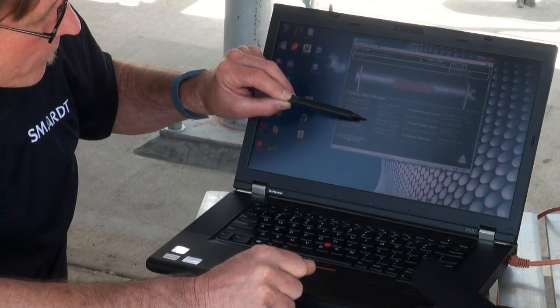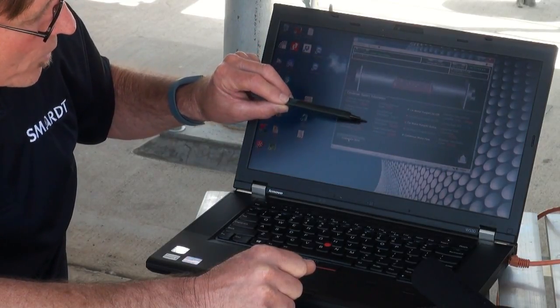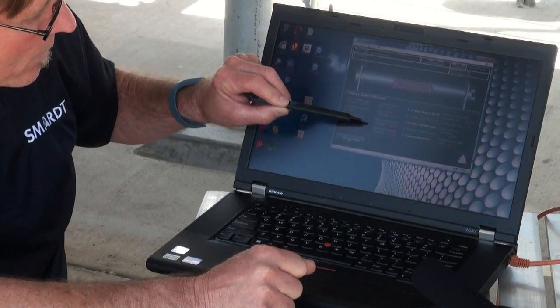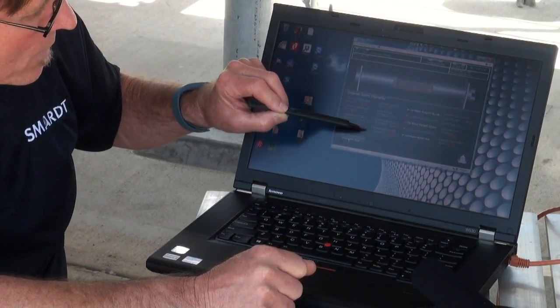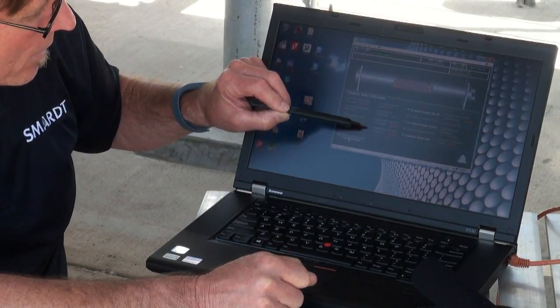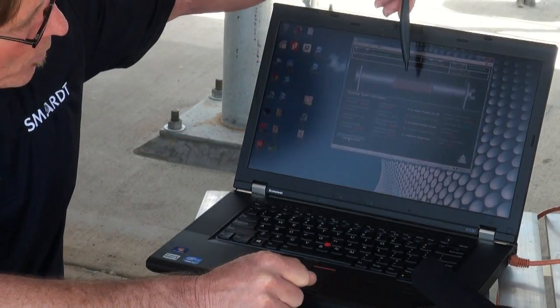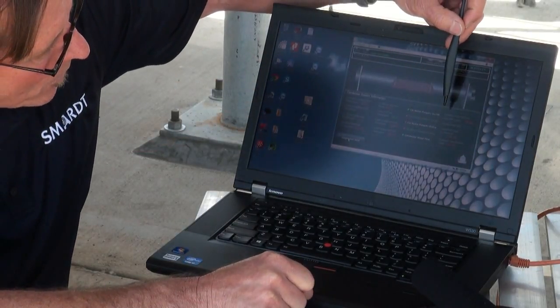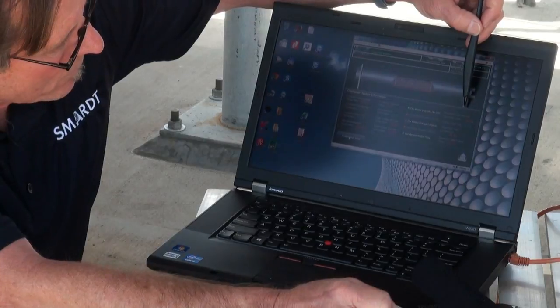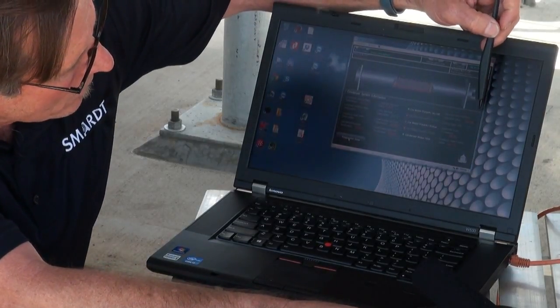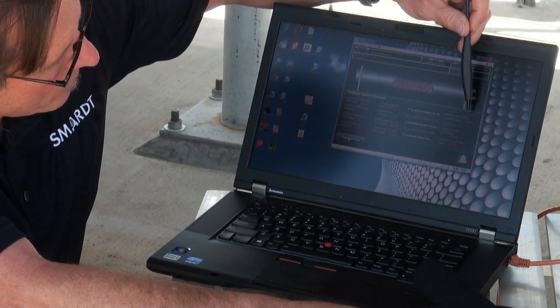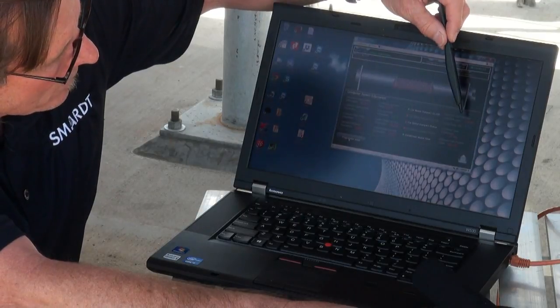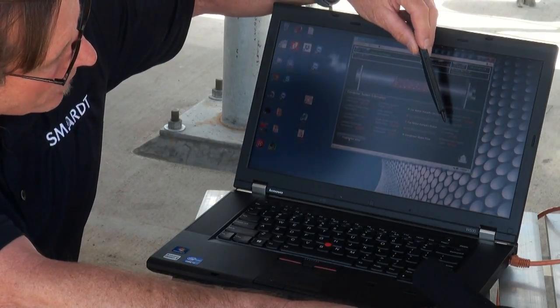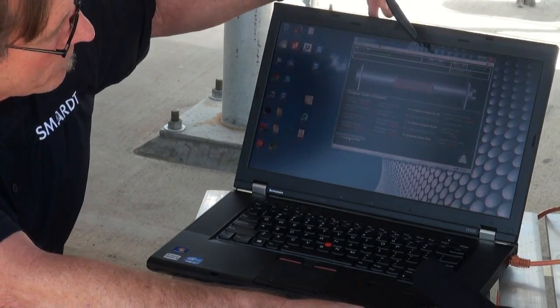You've got, of course, if we're controlling the fan, I don't know if we were controlling with the Kiltech controller, but this has the capability of controlling the fan, your set points, and also condenser pumps. We can control condenser pumps if need be. Again, we have expansion valve information. We have level, set point, and actual level, and expansion valve position.